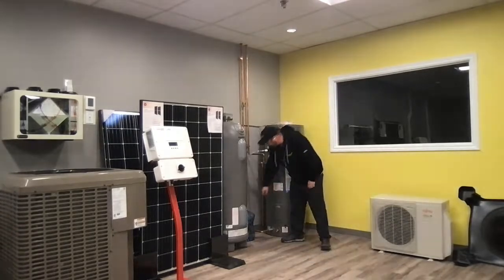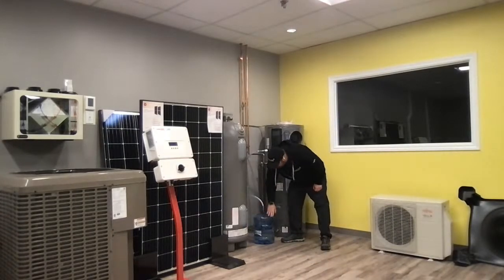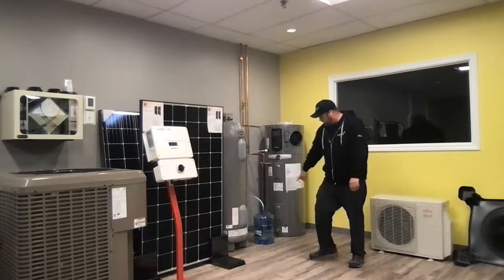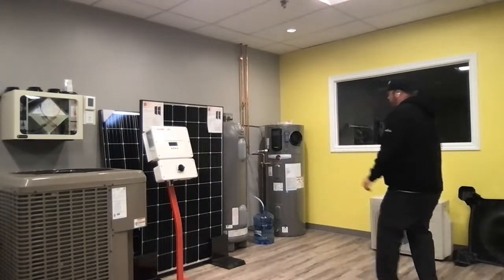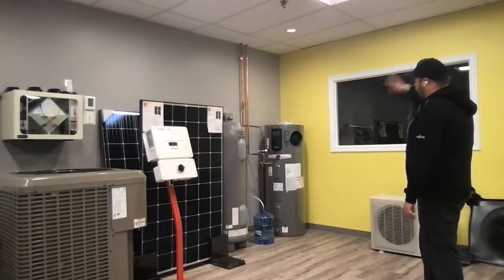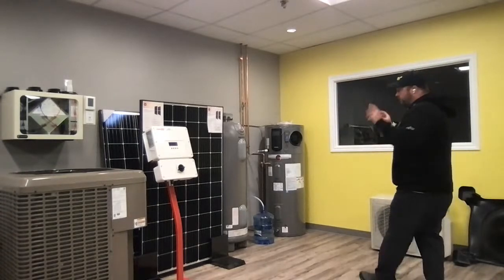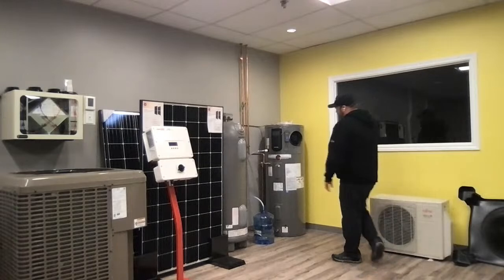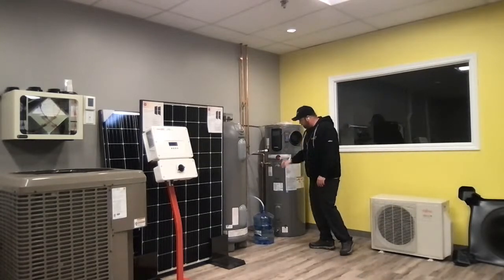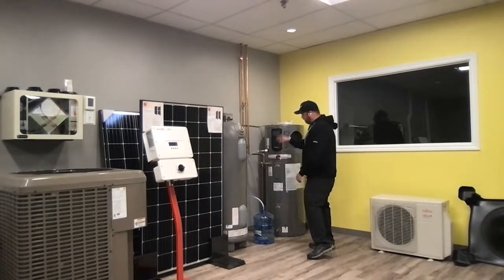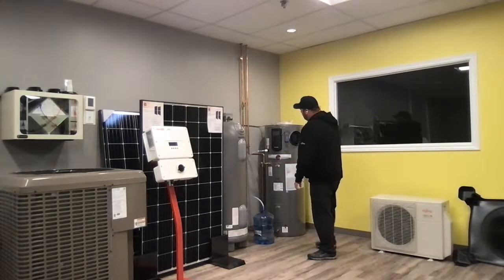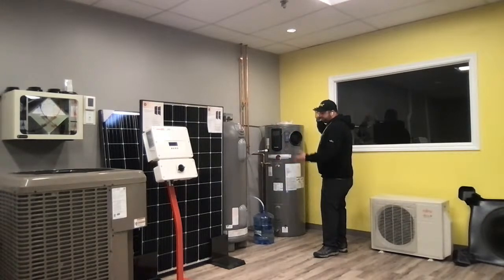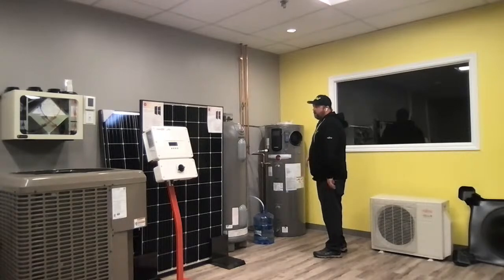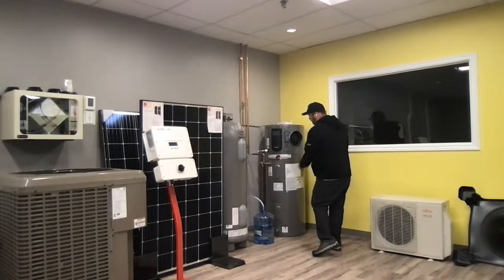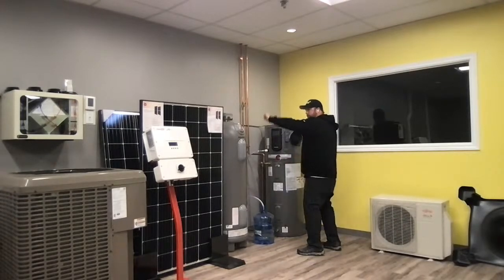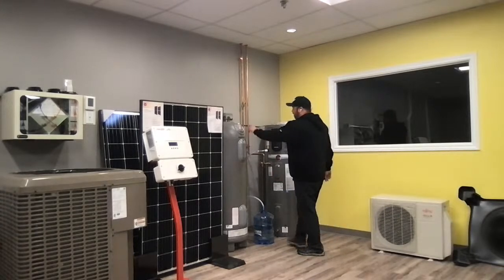It's a much more complicated install. This one's hooked up to a bottle of water, so you can see that when we're heating our water here, for the little that we actually use in the office, that water coming through here is condensing. We have to get that water somewhere, so you need a drain nearby, or a laundry tub, or we have to put in a condensate pump, just like a ducted heat pump, and pump it somewhere to get the water out.